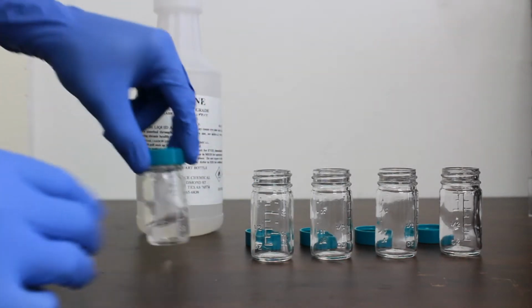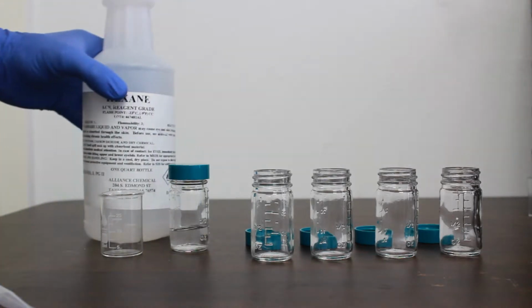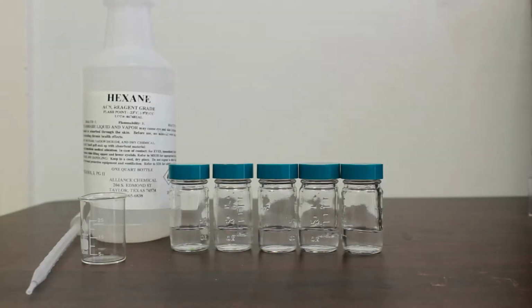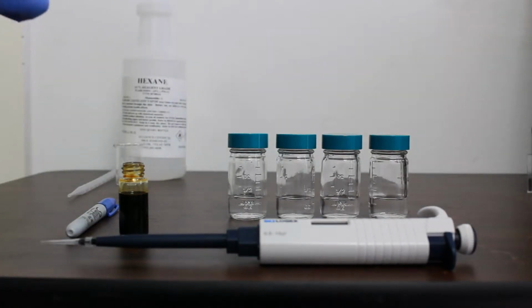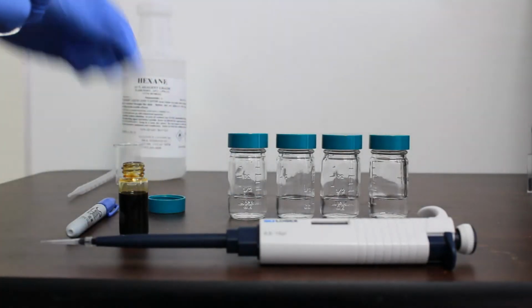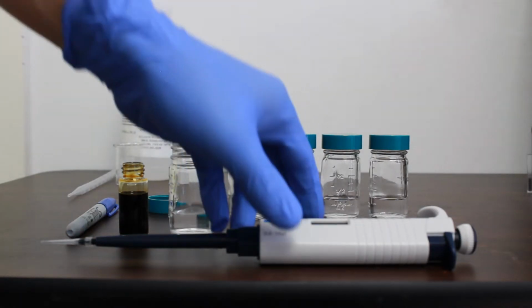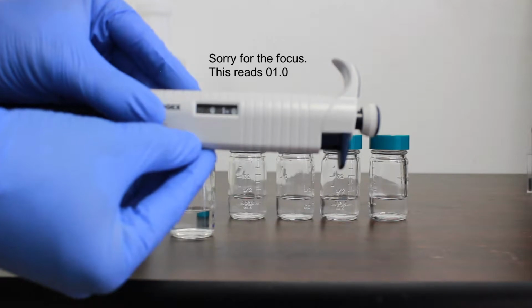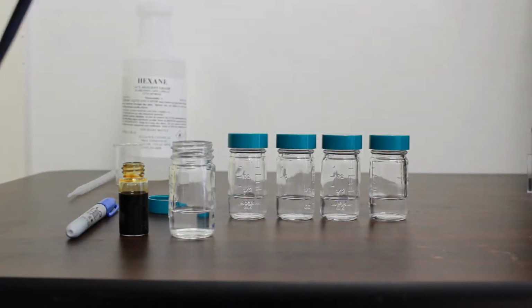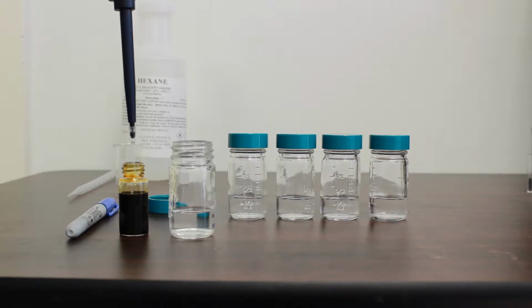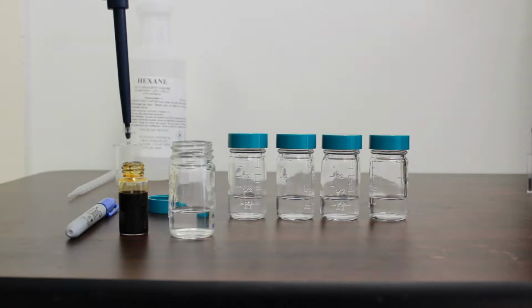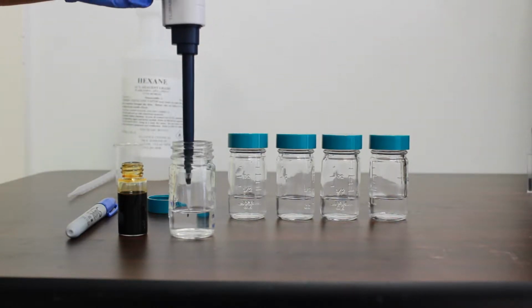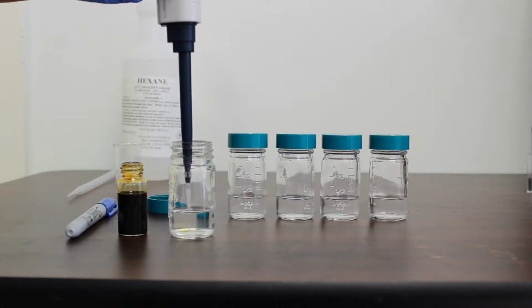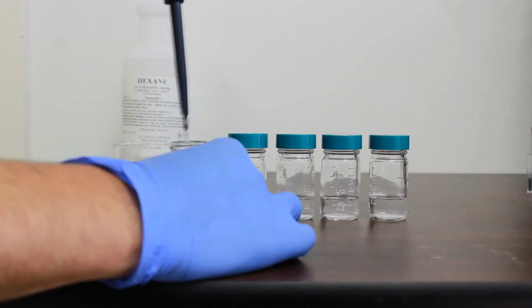When all of your standards containers have hexane, you can move on to the step of making standards with your particular type of oil. Oil can now be added to each of the standard containers using the micro pipette included in your kit along with pipetter tips. Also included in the OWB user manual is a sample prep spreadsheet, which gives volumes of oil to be added to volumes of hexane in order to get specific oil concentrations for calibration. An easy conversion to remember, though, is 1 microliter of oil added to 10 milliliters of hexane gives a 100 ppm standard.